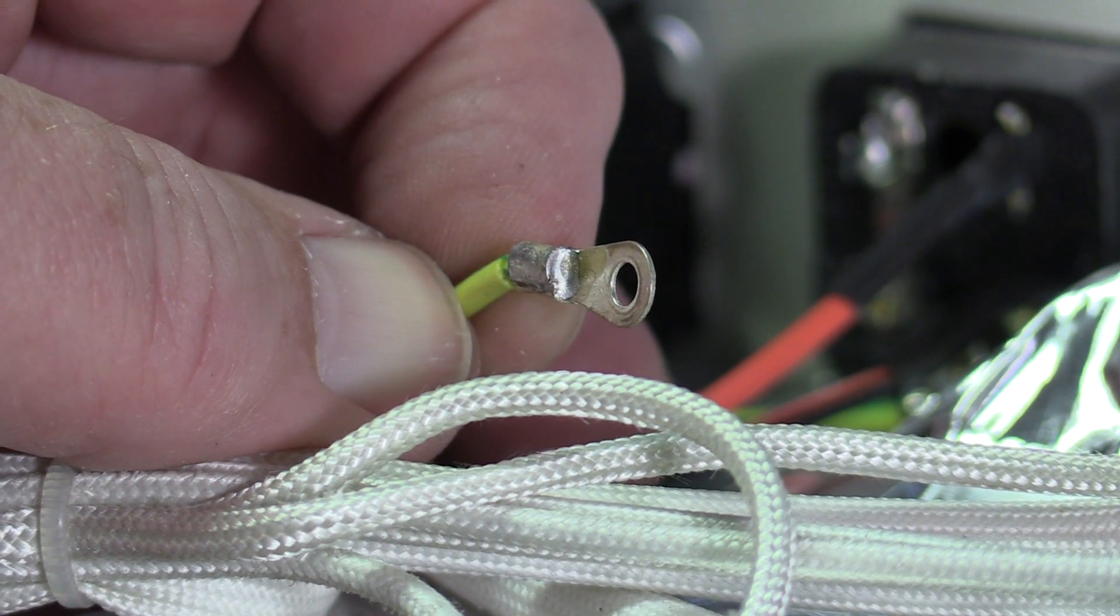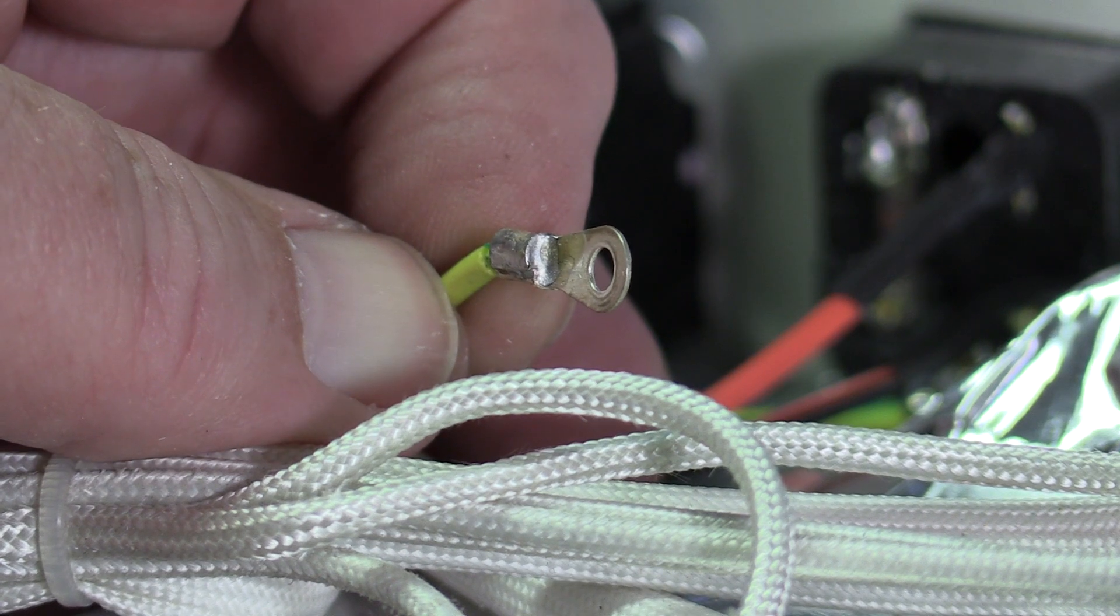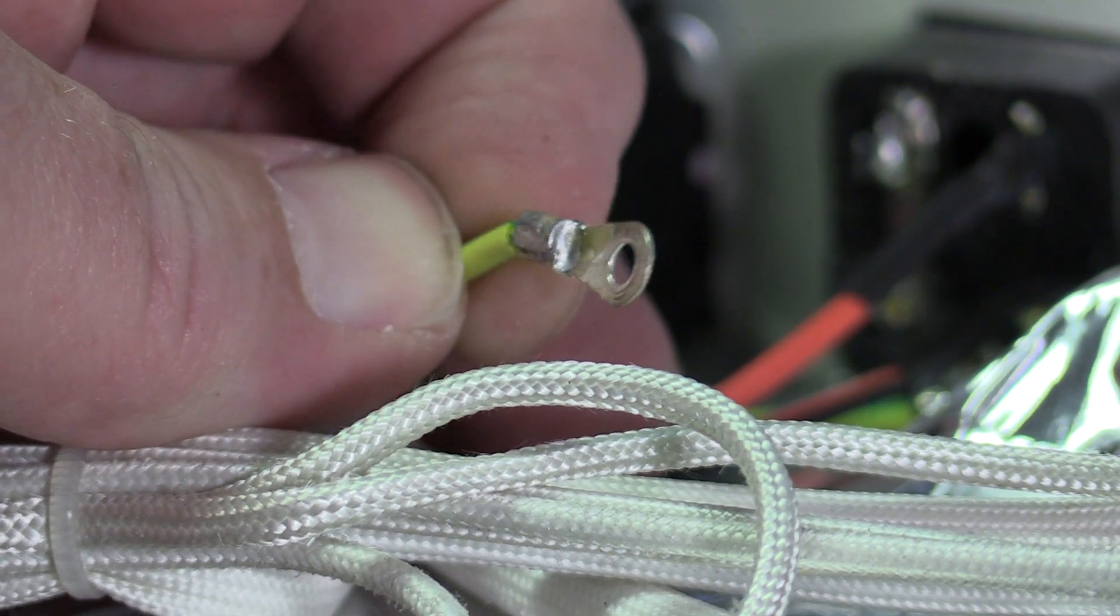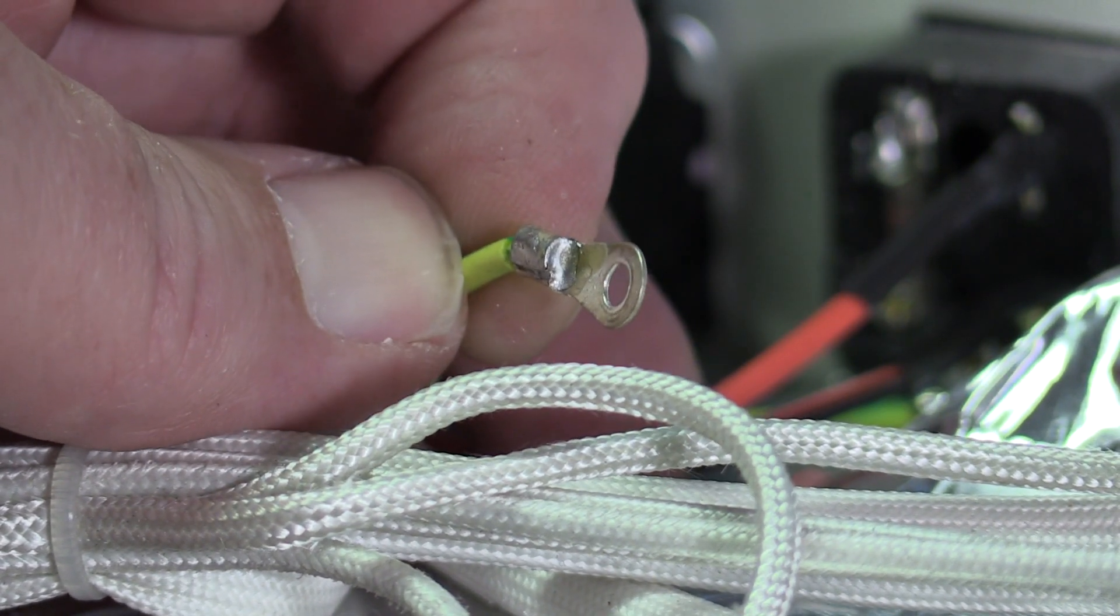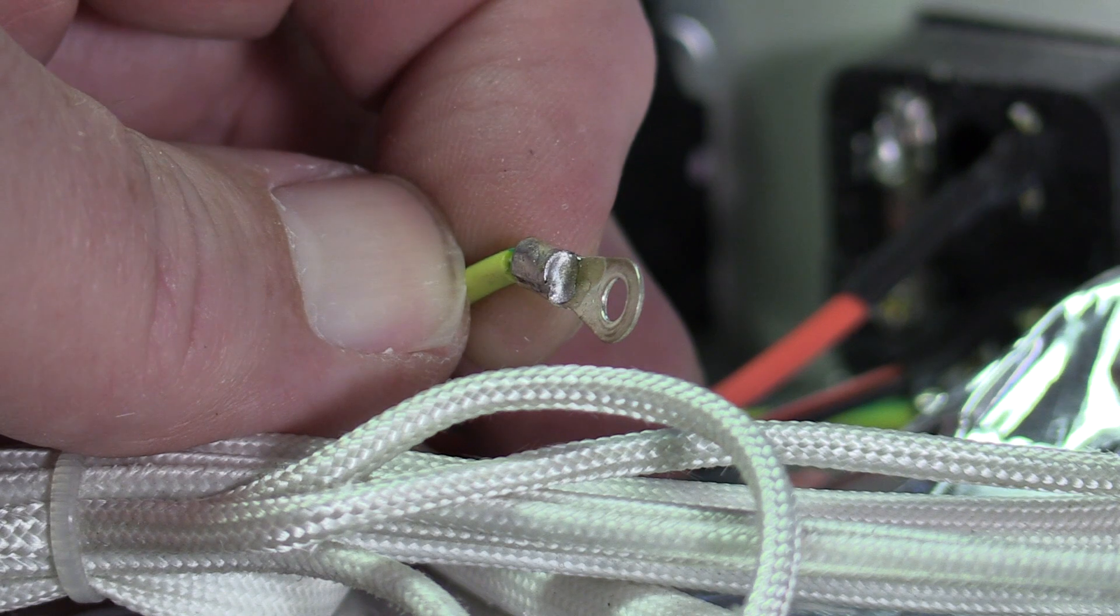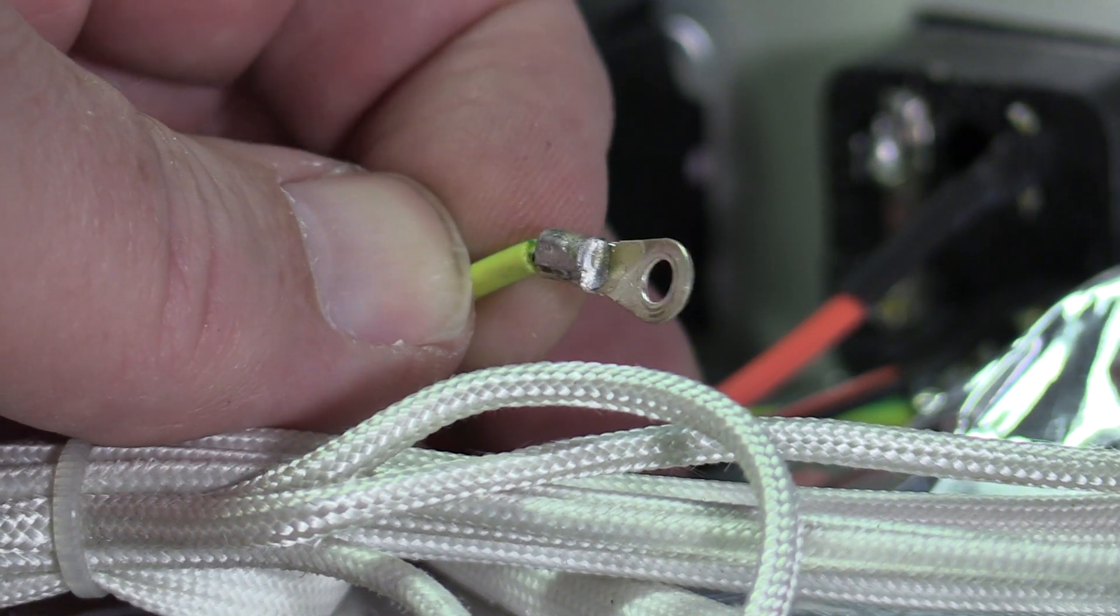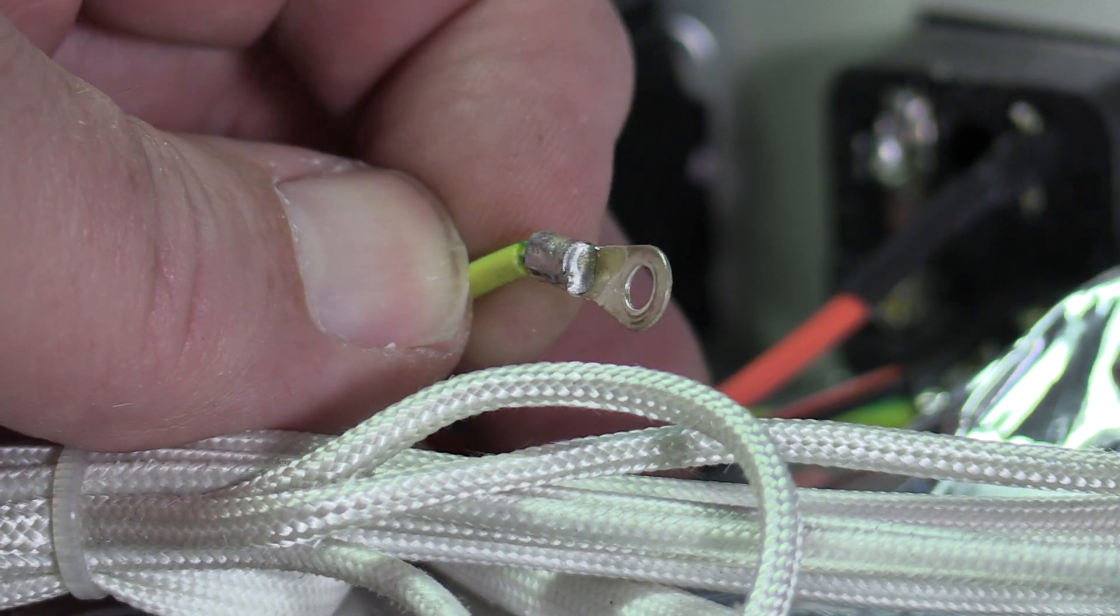It looks like instead of taking the right ring lug and crimping it on with the right tool, this is kind of crimped over with a pair of pliers and then soldered into place. That's not how you normally want to handle a safety-critical grounding wire.